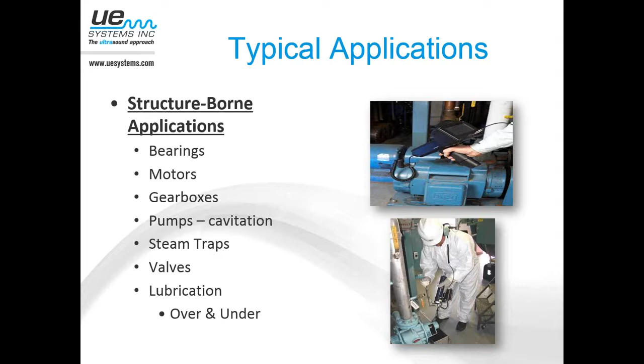And lubrication, condition-based lubrication, whether we're in the process now of trying to optimize time-based lubrication, where we're trying to determine the interval to go out and lubricate, or whether we're really moving into some best practices of condition-based lubrication, where we identify the need to lubricate rather than base it on time, base it on the condition of the asset, and then go out and make sure that we're not putting too much grease in. So again, some typical applications of ultrasound. I'm going to start and just talk a minute about energy conservation.